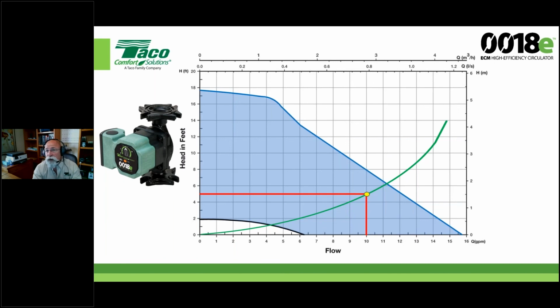And again, we'll turn it down when we get the feedback from the boiler manufacturer that gives us the delta T under a design load condition. So those are good. You go out on a job, you're just starting a boiler up and it's really cold and you've got some really cold water coming back from a high mass slab. You can put that boiler in a design condition. That means the maximum firing rate it's ever going to see under a normal design condition, right? So anyway, that's what we want to try to simulate.